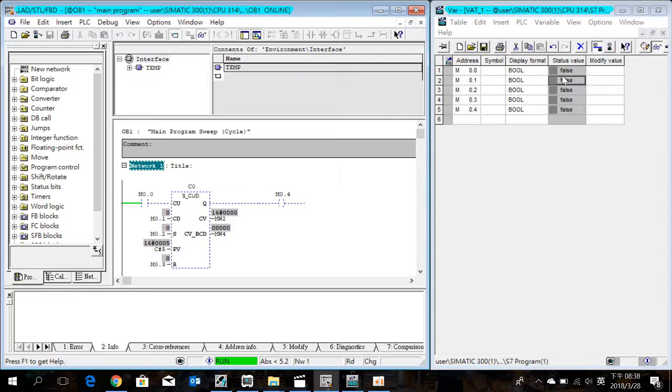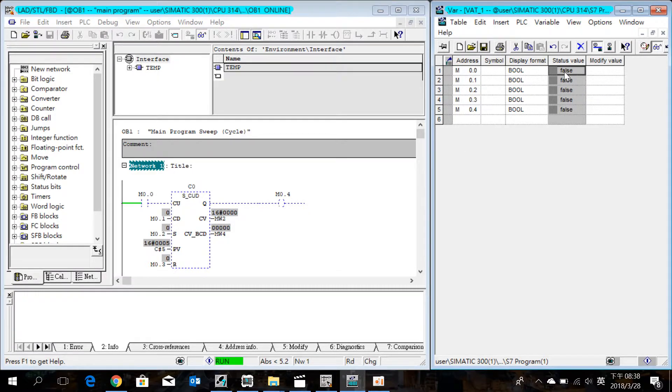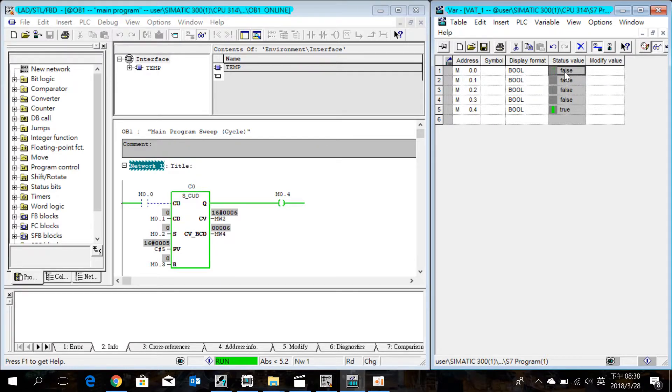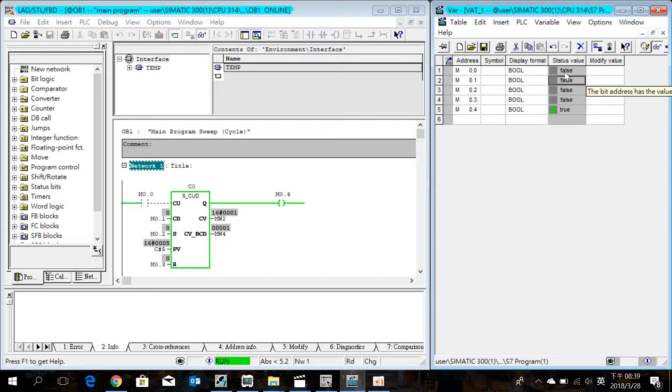Okay, let's check the M0.0. Each time M0.0 is triggered, MW4 will increase by 1, and the coil M0.4 will always be on if MW4 is more than 1. When MW4 is less than 1, then the M0.4 will be off.